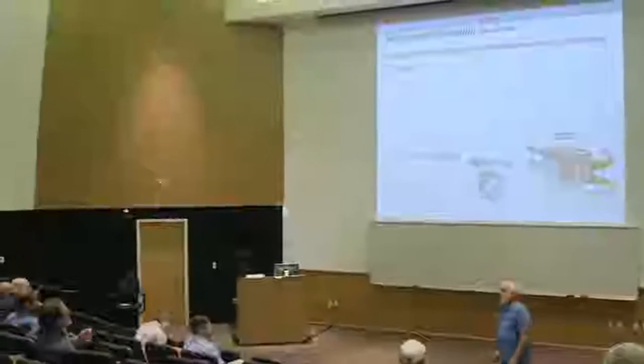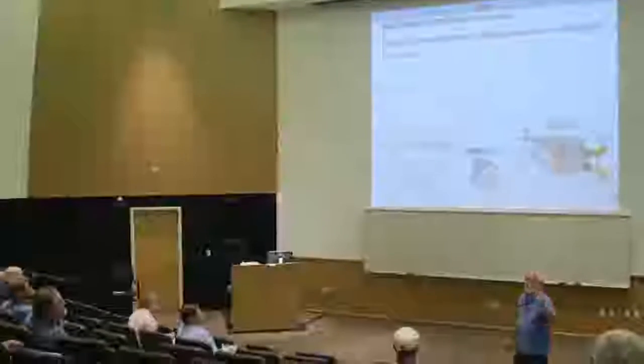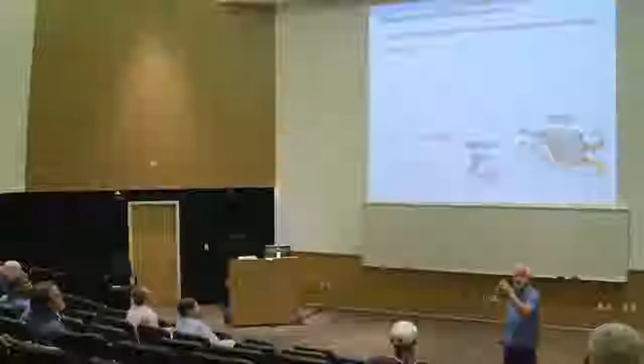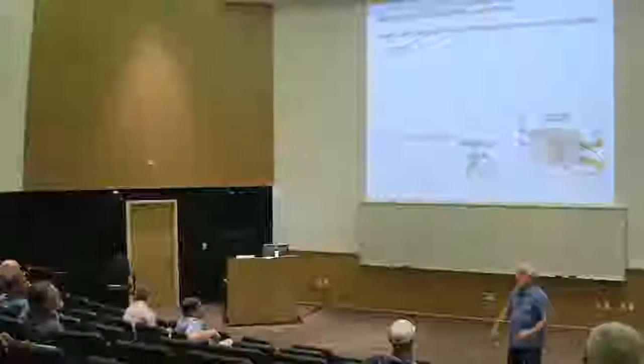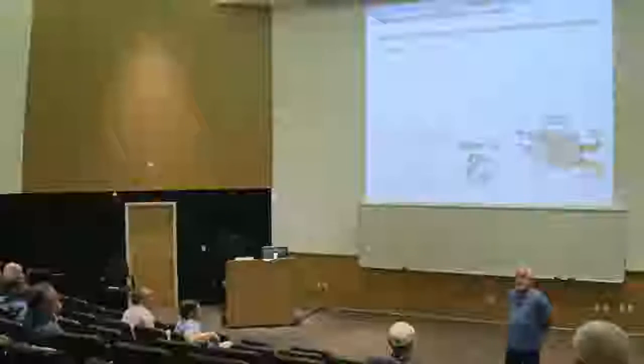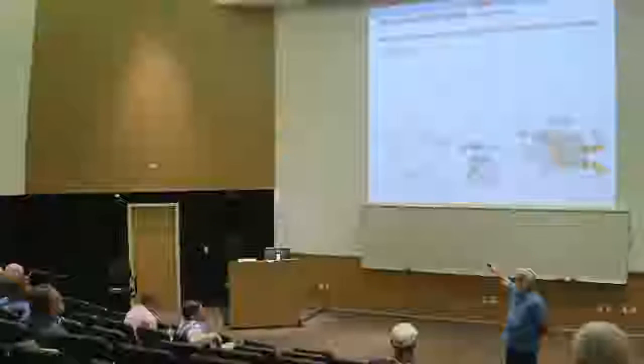The second option, I'll go into this in a little more detail. The second option is an exhaust fan. Remember I said we can do supply or exhaust or a combination of supply and exhaust. So exhaust means that we constantly remove a little bit of air out of the space. So you can put in a fan that just runs all the time at the 30 or 40 or 50 or 60 CFM you need for ventilation for that house, and hardwire it so it runs all the time. And that's a really cost-effective method to do it.